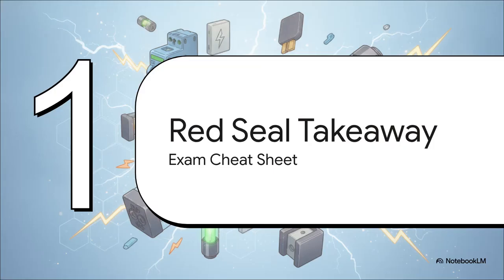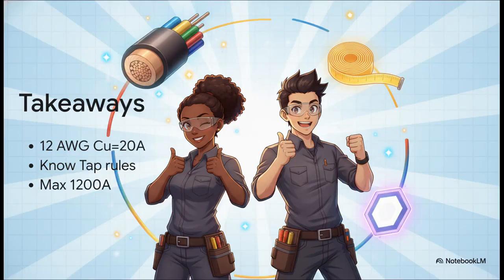And that brings us to the most important part of this explainer, the Red Seal takeaway. This is your ultimate quick reference cheat sheet for Section 14. Make sure you lock these 3 things in before test day. Number 1, know Rule 14-104 Sub-Rule 2 inside out. 14 AWG copper is 15A, 12 AWG copper is 20A, and always watch out for aluminum. Number 2, memorize those 3 meter and 7.5 meter exceptions in the tap rules under 14-100, especially that 1/3 ampacity rule. And number 3, dodge those ground fault traps in 14-102. Remember the 1200 amp maximum setting and the 1 second maximum delay.